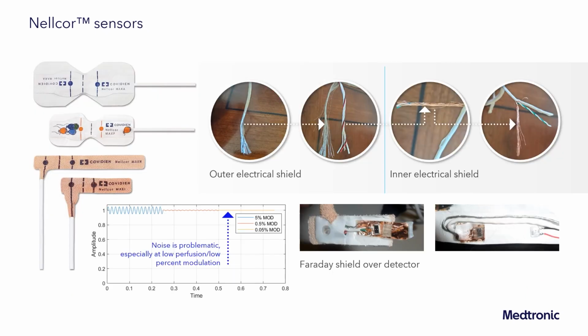And for a pulse oximeter to work well, we have to go back to our system level thinking of that pulse ox, and everything has to be designed to be able to deliver that performance, and it starts with the sensor. Here at Nellcor sensors, I like to show this example because Nellcor is rated down to a percent modulation of 0.03%. Here we're showing stepping down from 5 to 0.5 to 0.05 in that plot in the lower left-hand corner. You can see comparing 0.05% modulation to 5% modulation is tiny. A little bit of noise that gets on that signal will wreak havoc in the processing later on.